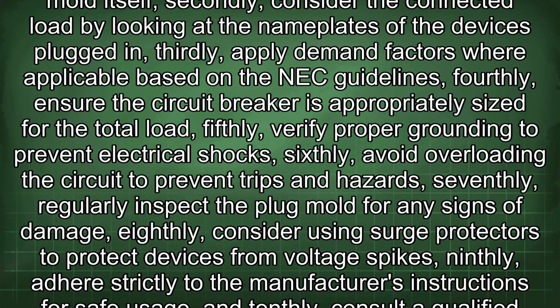In summary, to calculate volt amps for plug molds, you should firstly determine the rating of the plug mold itself. Secondly, consider the connected load by looking at the nameplates of the devices plugged in. Thirdly, apply demand factors where applicable based on the NEC guidelines. Fourthly, ensure the circuit breaker is appropriately sized for the total load. Fifthly, verify proper grounding to prevent electrical shocks. Sixthly, avoid overloading the circuit to prevent trips and hazards.